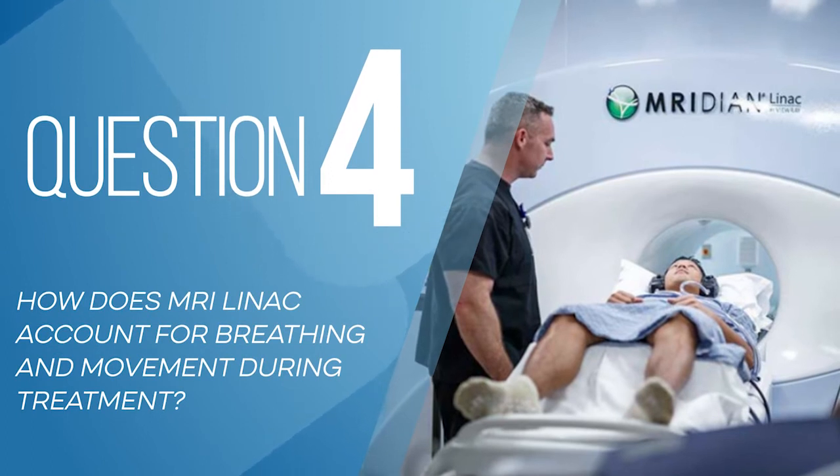I know that you work with lung cancers and the lung moves and the tumors move. How do you deal with that with MRI-Linac? With the MRI-Linac, one of the other advantages we have is called gating. The way we traditionally treat a lung tumor is that we have to treat a very large area anywhere the tumor can exist in the respiratory cycle, because your lungs are moving and your diaphragm is moving. With this MRI scan, the software will pick up the tumor, track it in real time, and the radiation will only turn on when the tumor is in the exact right position. That allows us to decrease our treatment volumes, spare normal organs and normal tissues, and hopefully decrease side effects as well. That's really critical for people who have compromised lungs or other conditions where we're trying to spare normal organs with treatment.